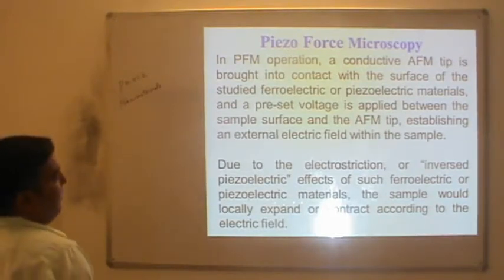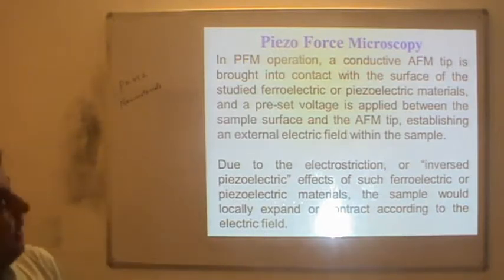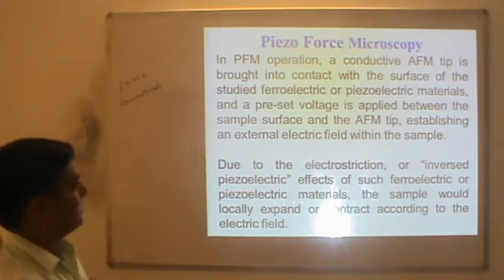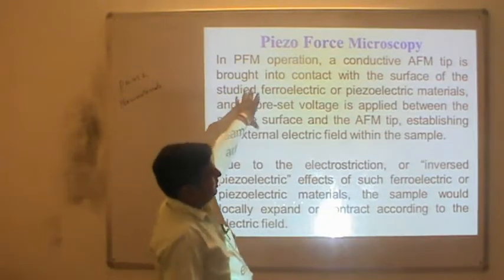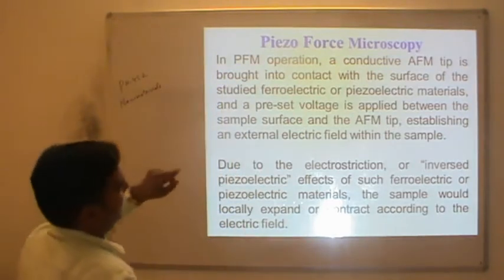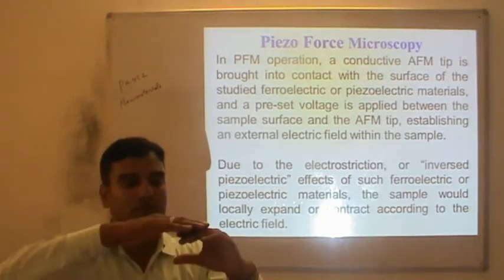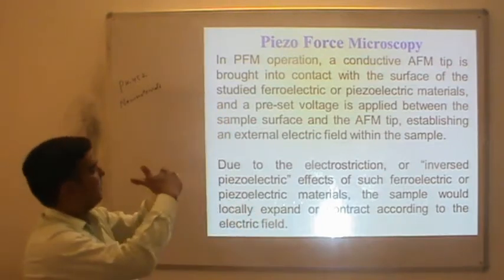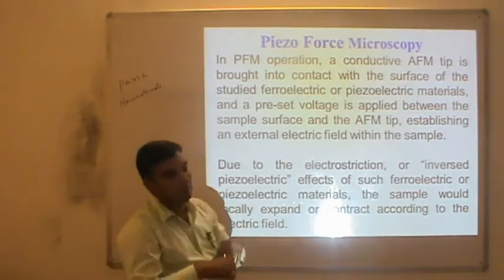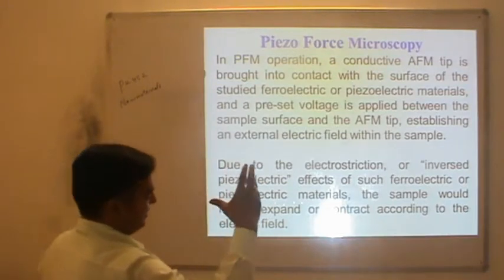In PFM operation, a conductive AFM tip is brought into contact with the surface of a ferroelectric or piezoelectric material, and a preset voltage is applied between the sample surface and the AFM tip — establishing an external electric field within the sample. As we apply this voltage between the tip and sample surface, an external electric field is generated.